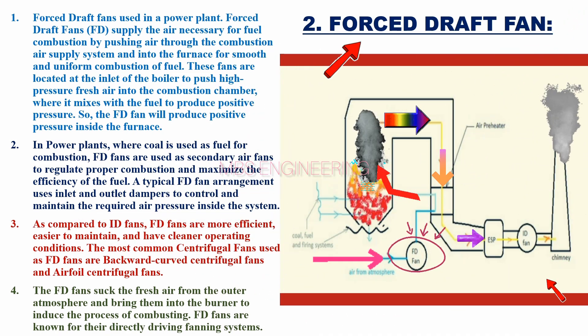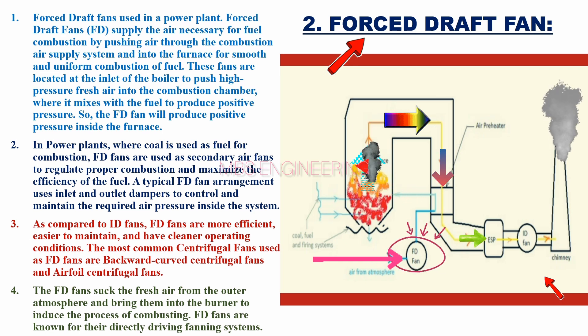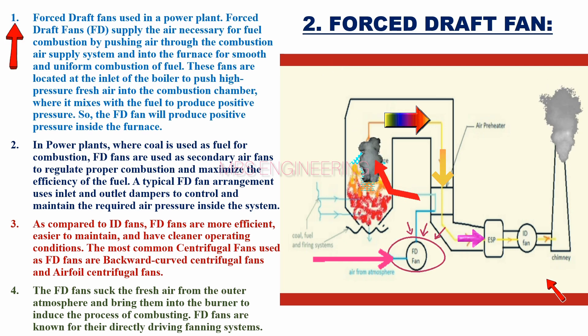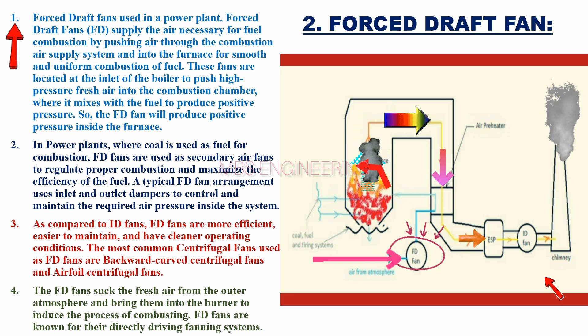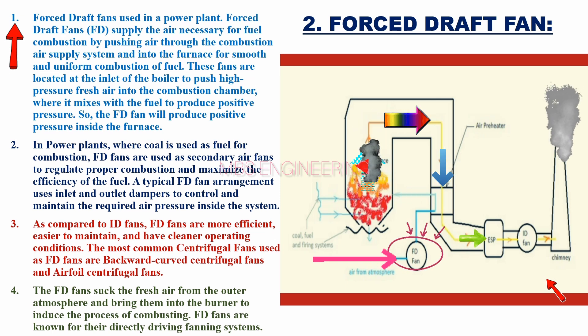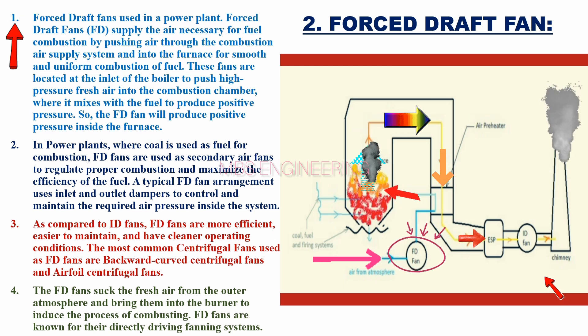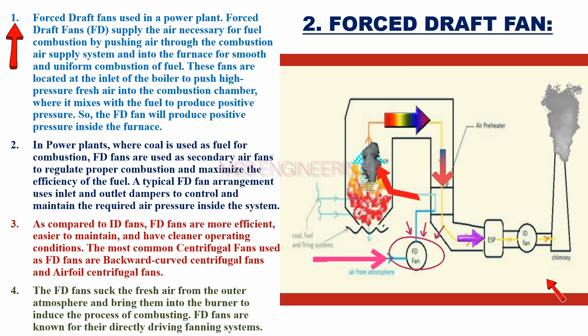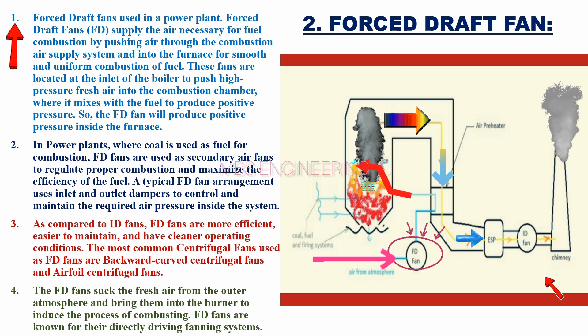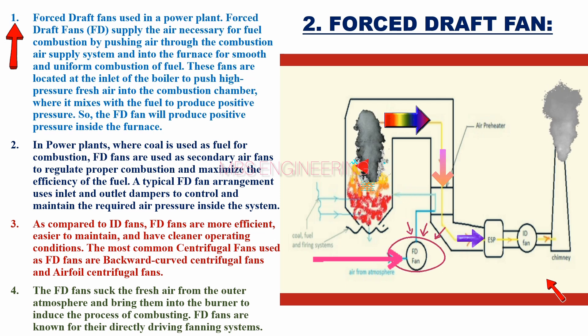Let's move on to the FD Fan. Forced Draft Fans supply the air necessary for fuel combustion by pushing air through the combustion air supply system and into the furnace for smooth and uniform combustion of fuel. These fans are located at the inlet of the boiler to push high-pressure fresh air into the combustion chamber, where it mixes with the fuel to produce positive pressure. So the FD Fan will produce positive pressure inside the furnace.